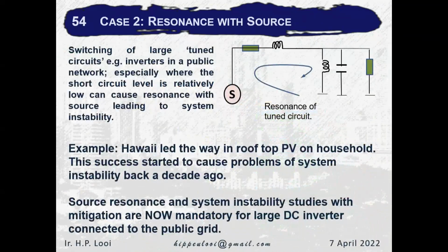So, yeah. Now, resonance with source. A good example is if you have a lot of PV; the example was Hawaii a decade ago. They were the leader in mounting PV, because Hawaii's electrical system is relatively small. That means their generation level or short circuit level is much lower than ours. If you have a lot of PV, when you switch on the PV, it is going to cause system instability. Because of that, a resonance study is actually a requirement if you are installing a large PV installation in Malaysia.